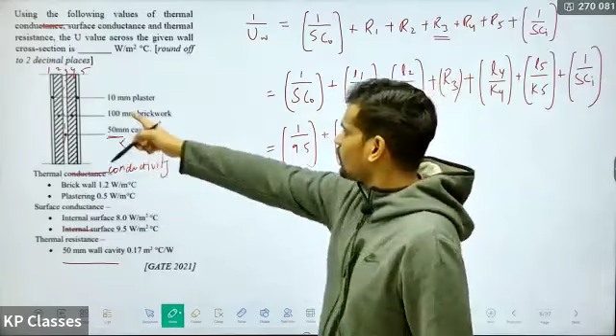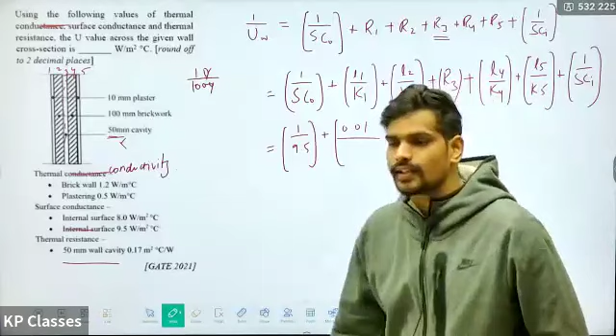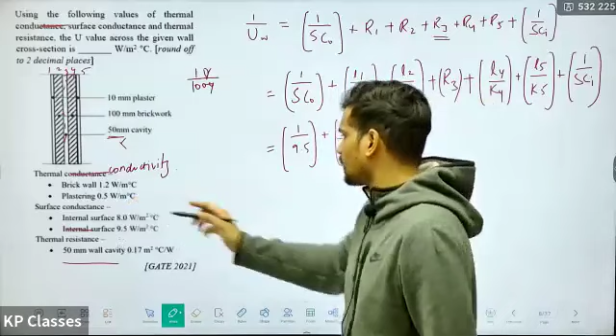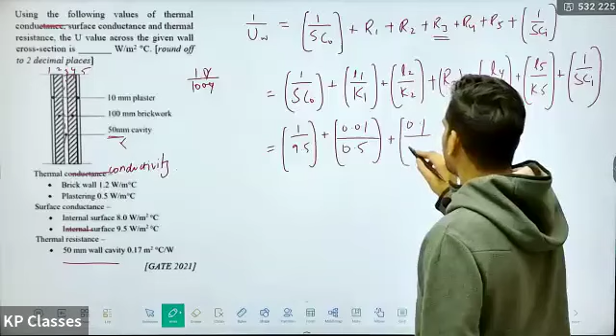You need to convert that 10 millimeters into meters. So 10 mm in meters will be 10 divided by 1000, so that will be 0.01, the thickness in meters, divided by K of the first layer, the thermal conductivity of the plastering layer, which is given as 0.5, plus for the second layer, it is brickwork, 100 mm can be written as 0.1 meters divided by the conductivity 1.2, plus for the third layer, R3 is directly given, 0.17. You will add that without any thickness.